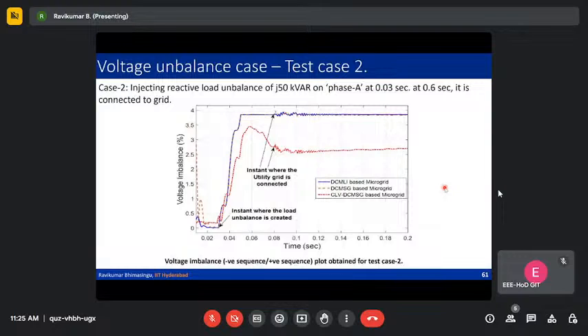This is another case to check the voltage unbalance. Here we are injecting a reactive load of 50 kVAr at phase A. It is created at 0.03 seconds and lasts until 0.06 seconds, at which point it is connected to grid. Voltage unbalance is measured in terms of the negative sequence quantity relative to the positive sequence quantity. We know we don't want the negative sequence quantity, so as less as possible.